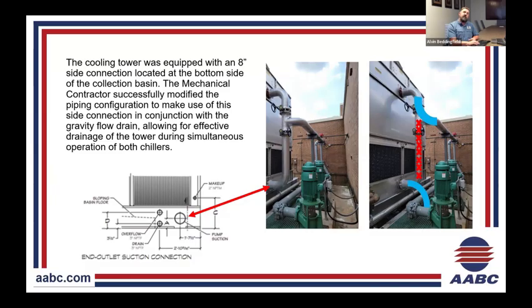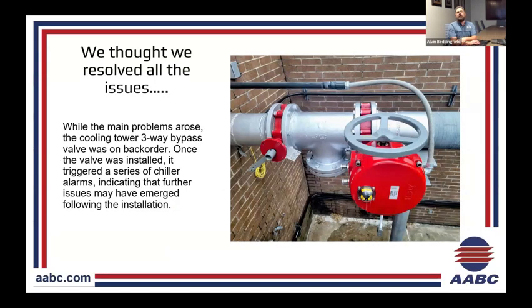So at this point, we finally were able to get the mechanical startup team in there, start up these chillers, try to start pulling the campus in for finishes and stuff like that. But it was a very invasive process of going back and forth. It's like we had flow issues, now we had no water, now we have water, now we have too much water, and trying to eliminate what can we do and what's the next mistake on this job just to get it done. So we thought everything was resolved, right? Okay, everything's fine. I mean, we got flow, chiller manufacturers, everything started up.